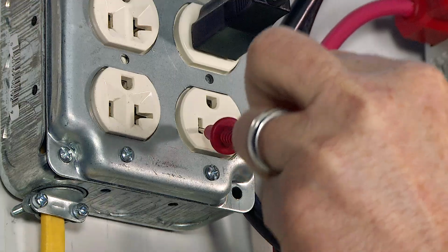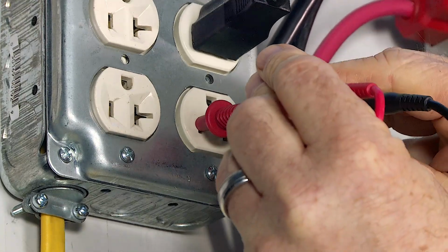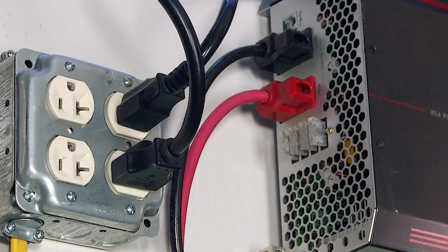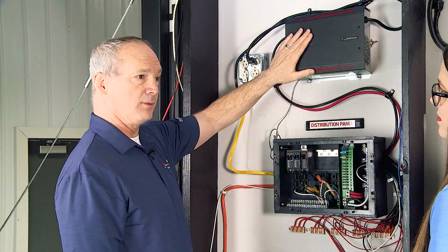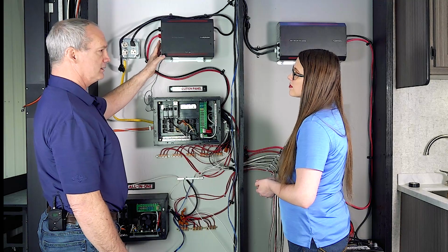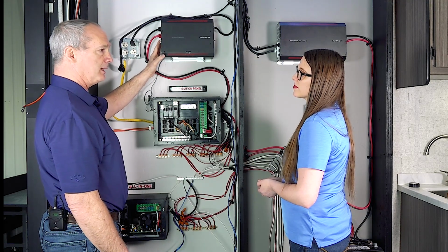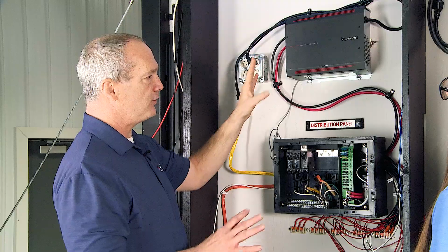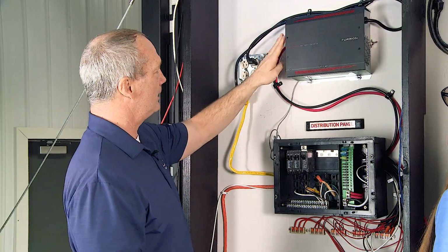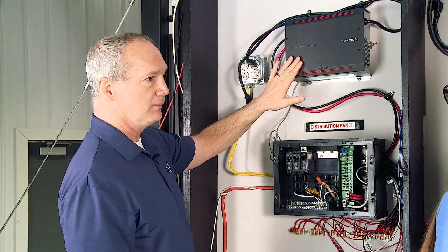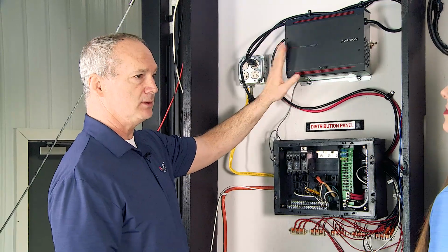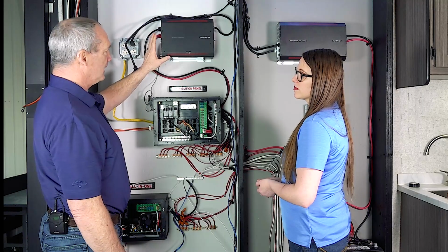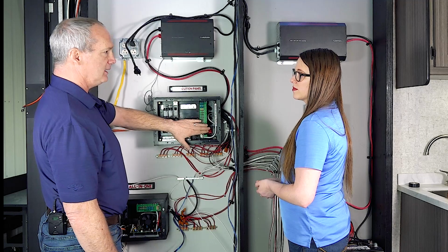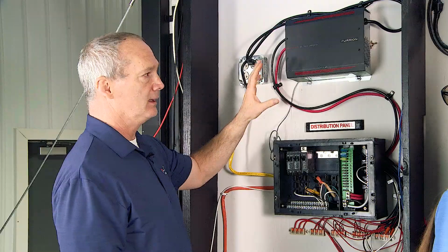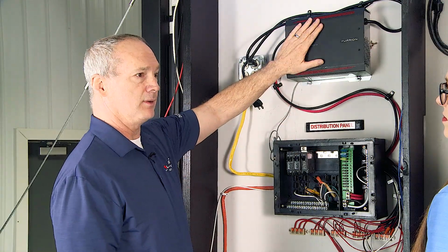So one of those four things, including the fuses on the converter. There's a series of fuses depending upon what converter you have, that you're going to check. You can pull those out, take a look at them, and make sure they're working. So those four points: the wiring, the contacts, the power into the converter, and the fuses. Once you check all of those, if you're not getting 12 volts DC here, it's going to be one of those things. And if it's not, then the converter's bad.